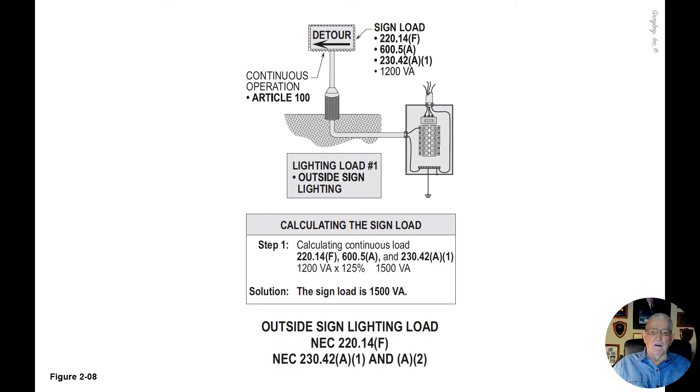220.14F, 600.5A and 230.42A1 are the sections that would be applied here. We would take the 1200 VA which is listed and take 125% which would equal 1500 VA.